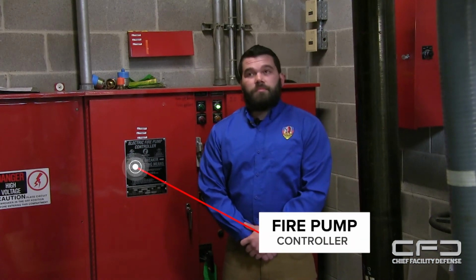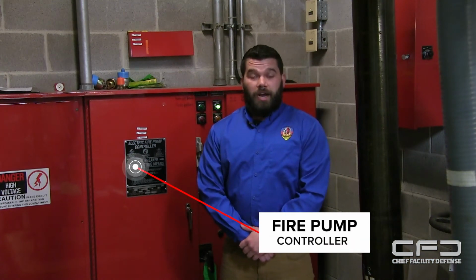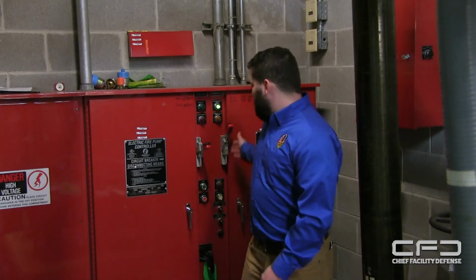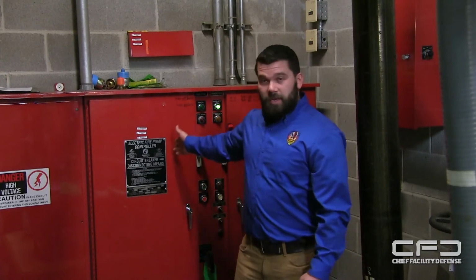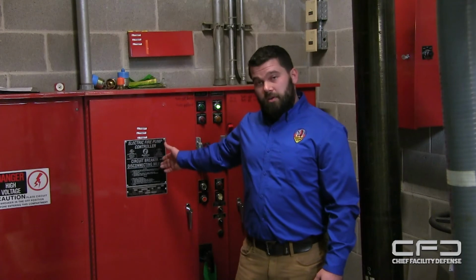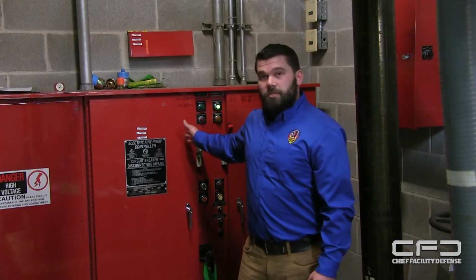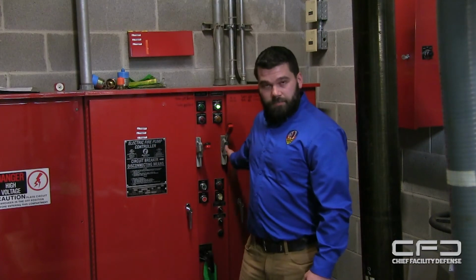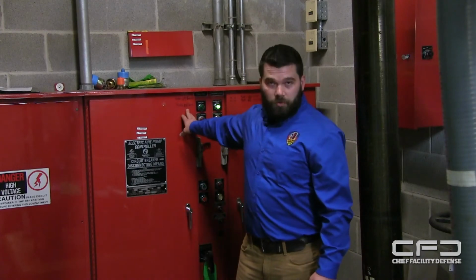Right behind me is the fire pump controller. In any case you would need to kill power to the fire pump, you would first turn off the emergency power and then the main power. To turn the pump back on, do it the opposite direction. You would turn on the main power, then turn on the emergency second, and everything is labeled accordingly.